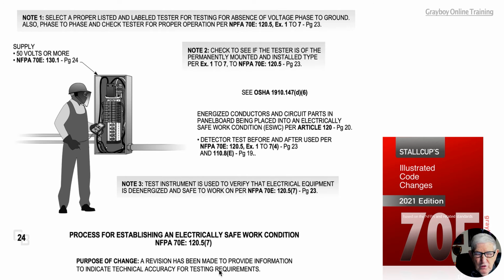Now remember, we previously in Article 110, reviewing 110.8A through E on page 19 of 70E, went through the basic general principles of testing equipment for safety. Now, let's review our notes first. Note 1 says select the proper listed and labeled tester for testing for absence of voltage phase to ground and also phase to phase. Check tester for proper operation, and we looked at that in 110.8E. But notice 120.5, the exception 1 to 7 on page 23, deals with testing the voltage for absence to lock and tag out.